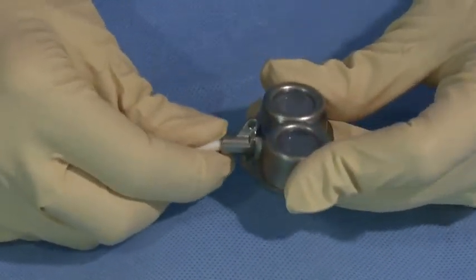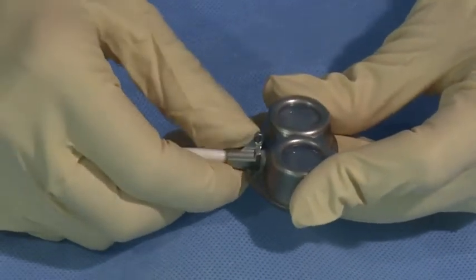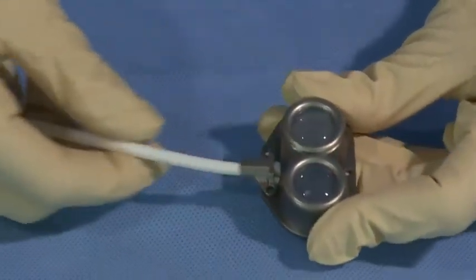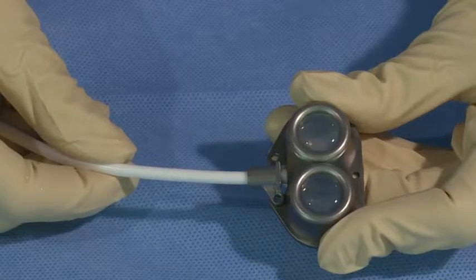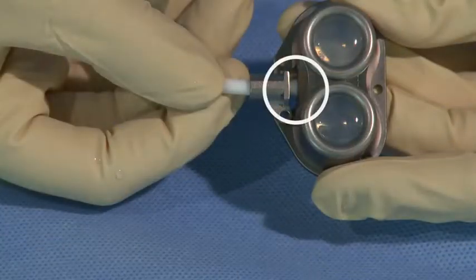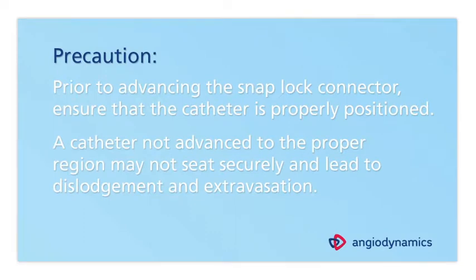Turn lock 90 degrees until suture tab lies flush with the port base, thereby locking the catheter into place. Note, with proper assembly, a short donut-shaped section of the catheter should be visible between the bayonet locking ring and the port body. Precaution. Prior to advancing any port locking mechanism, ensure that the catheter is properly positioned.